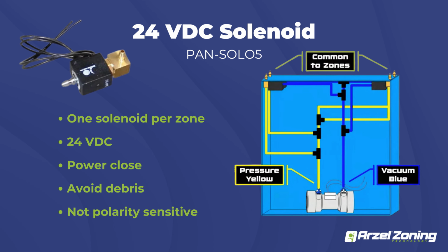So when you take a look inside our panel box in this picture here, this is how our tubing is installed. As you can see, we have a positive pressure tube and a vacuum pressure tube that come off the pump, and then it's going to split off and go up to little solenoids per zone. So every zone has its own solenoid, and that solenoid is what's actually going to switch the function of your damper. So if it's under a call and it's calling for conditioning, it's going to send vacuum to those dampers. And then all the zones that are not calling at that time, their solenoids are going to switch over to the positive pressure side of the pump. And that's how we end up closing the dampers on the system.